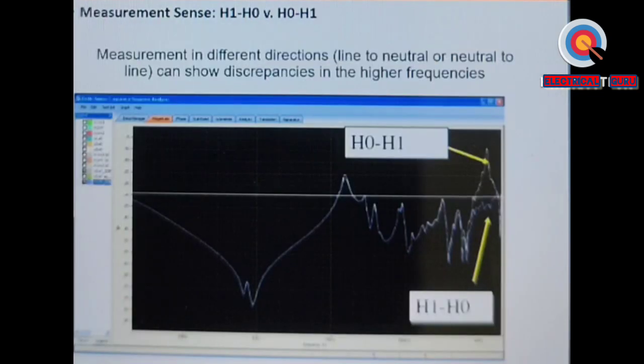This is where I was saying that the direction of the tap should be clearly noted, because if the direction changes, your graph can show you a distortion. So noting down the direction is very, very important. Here you can see it is H0 to H1, and this graph is H1 to H0. So if you are not conscious of the directions, you may have erroneous results, and then it can lead to wrong conclusions.